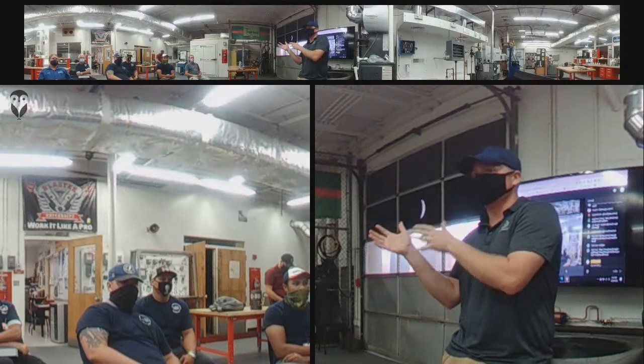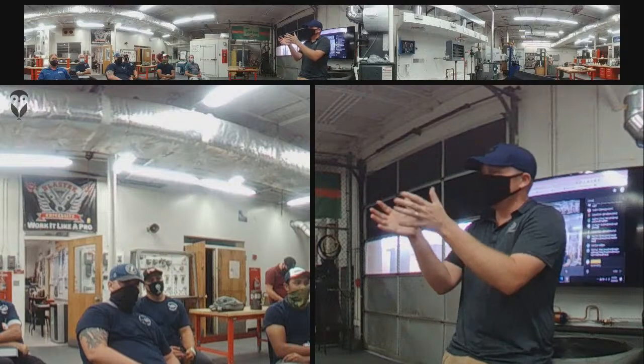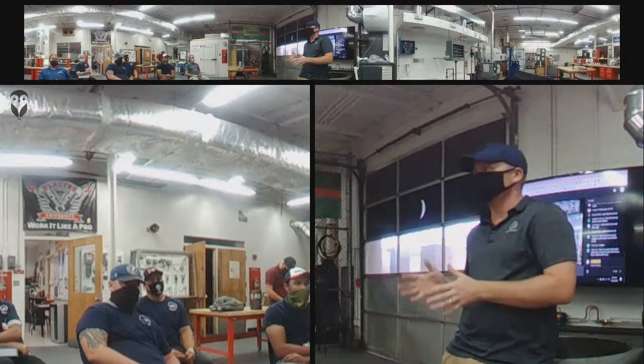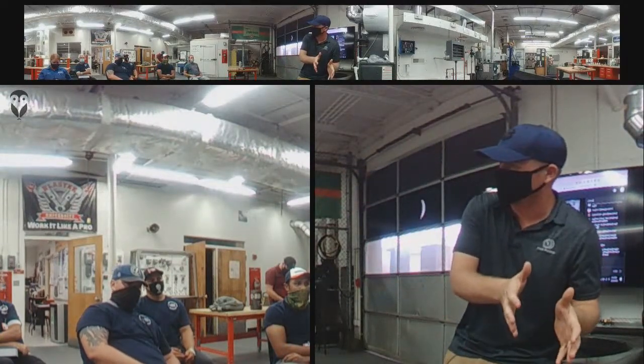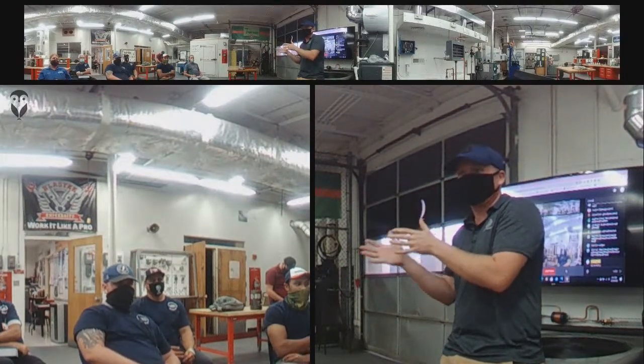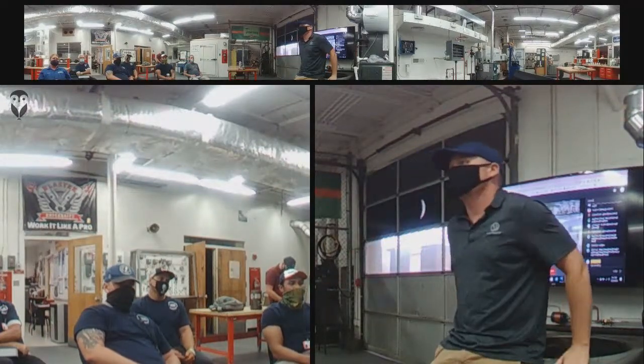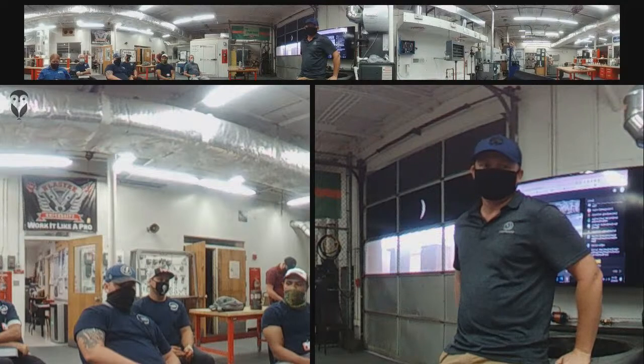And when you have lower than designed voltage, it can cause relays to chatter. Because if you drop the high voltage going into the transformer, you also drop the low voltage coming out of the transformer. So if you have it wired for 240 and you're only giving it 208, you're not necessarily going to have 24 volts coming out either. Always something to watch for in a commercial building.